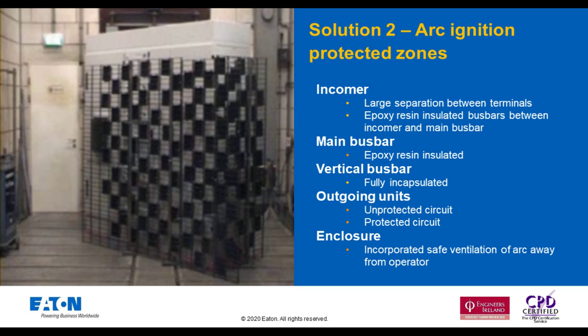The next criteria is criteria 2. This is where parts of the assembly which may cause a hazard do not fly off. So due to the pressure that's been generated within the enclosure, things don't fly off and hit the operator during the event of an arc fault. Criteria 3, arcing does not cause any holes to develop in the freely accessible external parts of the enclosure, so below 2 meters. So this is taking into account the average height of a person, as a result of an arc burning through materials.